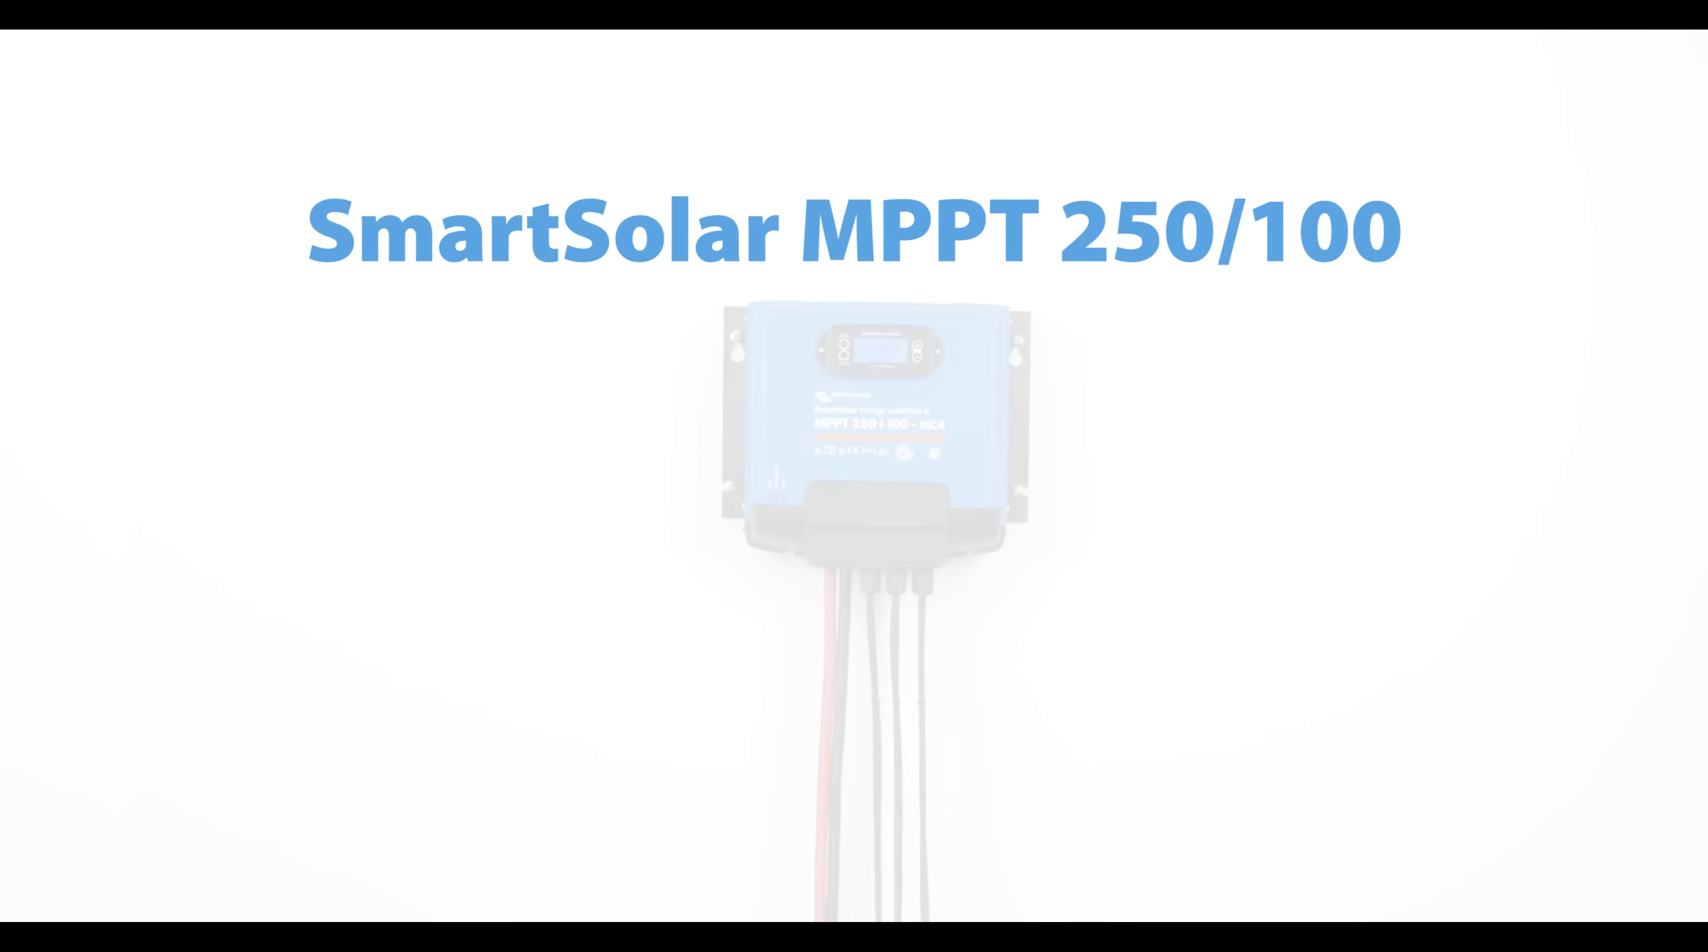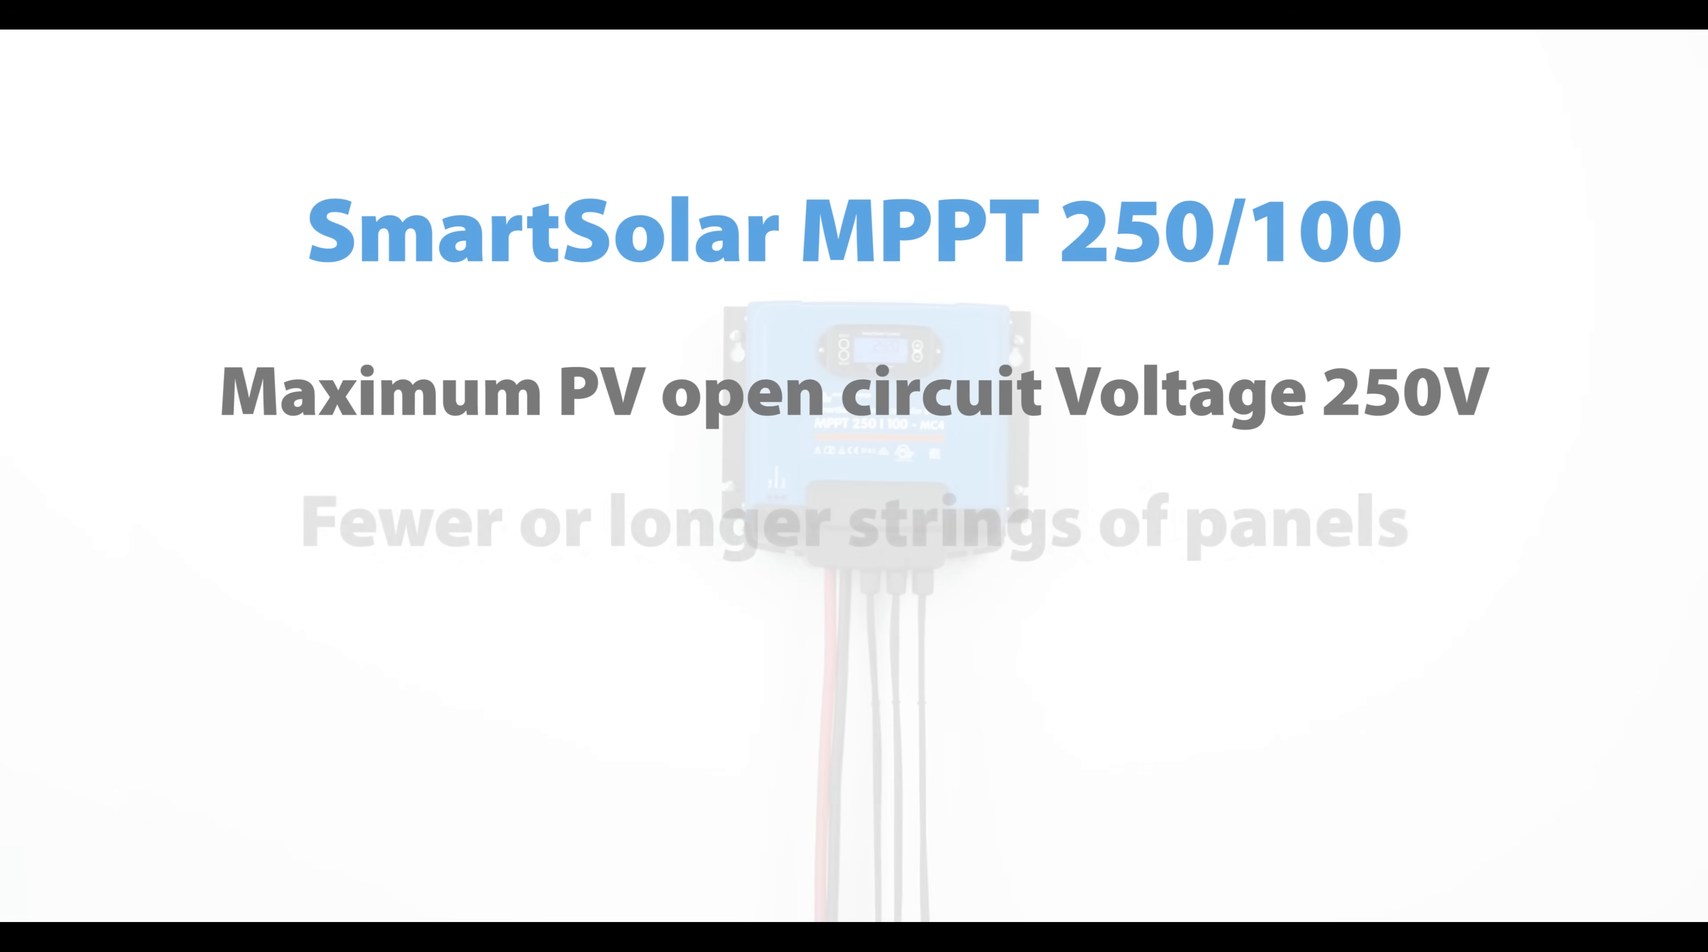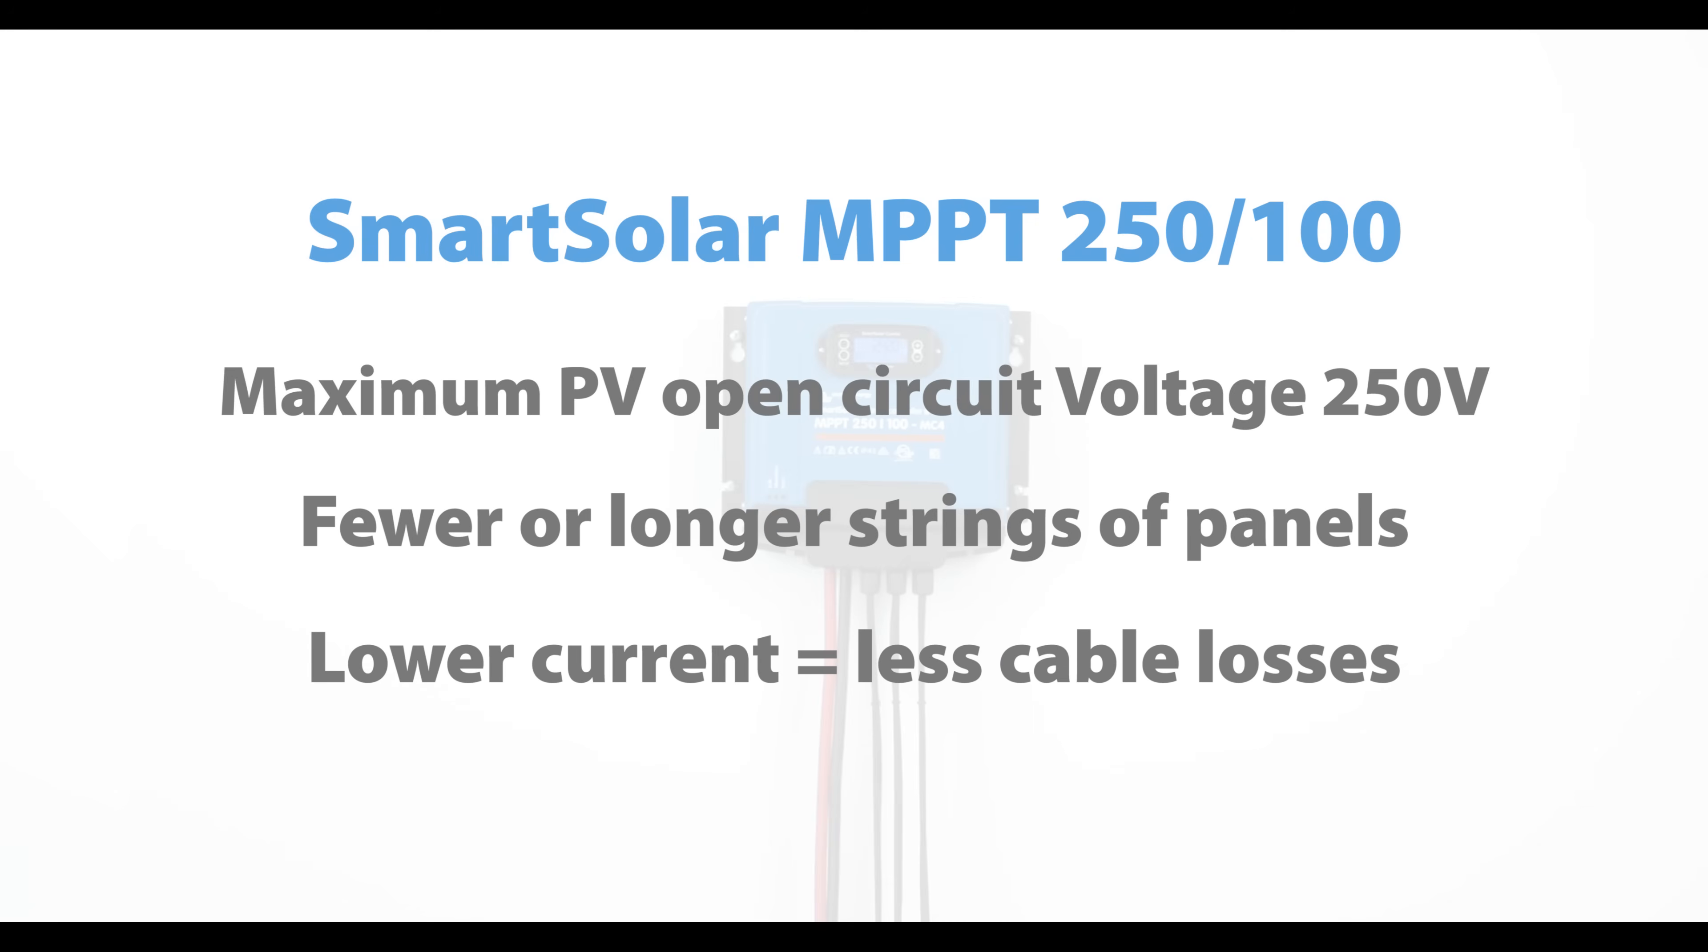With a maximum PV open circuit voltage of 250 volt, this Smart Solar model accepts the highest voltage of any MPPT in our range. This allows fewer strings of panels, or for those strings to be longer. Higher voltage means lower current, therefore less cable losses.